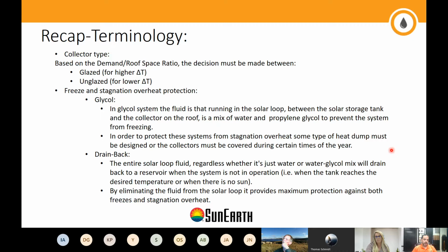Solar water heating systems are never designed to meet the entire load of the building or the applications, and there's a reason for that. This is usually when we talk about solar fraction, which we'll get to shortly. If we try to go for more than 70% of the entire demand — again, this is very general and doesn't apply to every case — the cost effectiveness aspect usually starts losing sense. So we have to be mindful of how much load we're looking at, where the project is being deployed, and what type of fuel we're replacing. All that goes into consideration before sizing the systems.